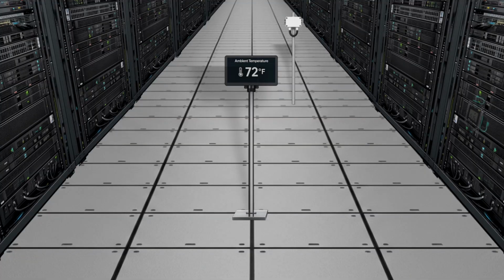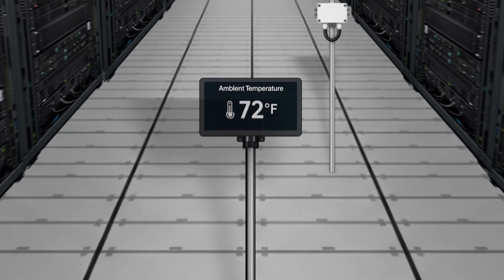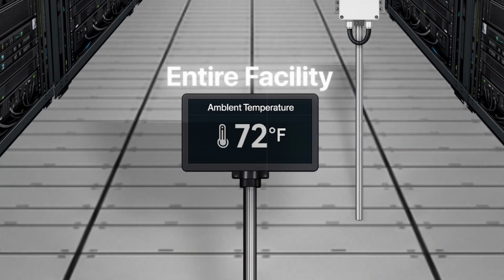So how do you fix it? Well, thankfully, it actually isn't complicated. You want to make sure that you're placing sensors at the locations that actually matter, like at the rack, at the aisle, or near the CRAC unit return, instead of relying on a single point of measurement to represent an entire facility. Now, on top of that, there's actually a module that's made specifically to combat this issue, but most engineers have never heard of it.